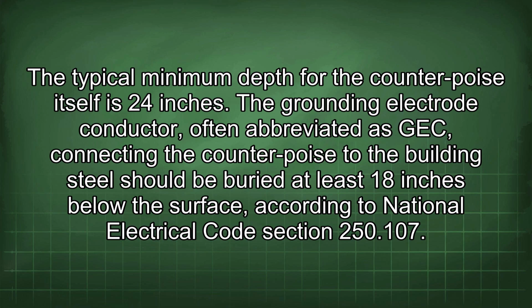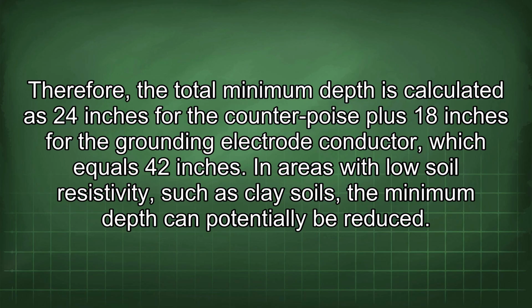The grounding electrode conductor, often abbreviated as GEC, connecting the counterpoise to the building steel should be buried at least 18 inches below the surface, according to National Electrical Code Section 250.107. Therefore, the total minimum depth is calculated as 24 inches for the counterpoise plus 18 inches for the grounding electrode conductor, which equals 42 inches.